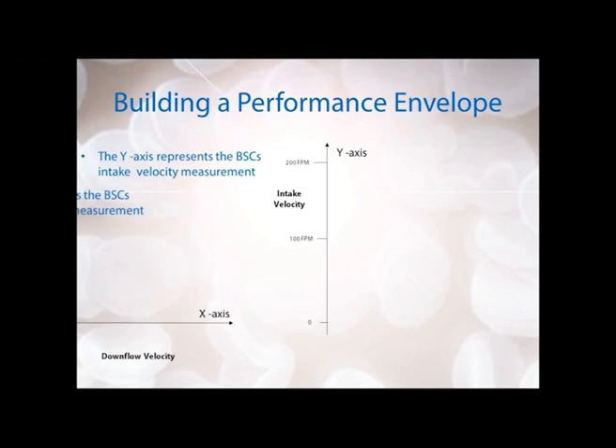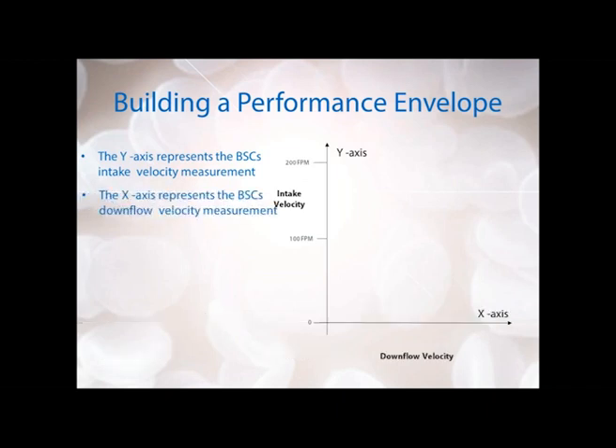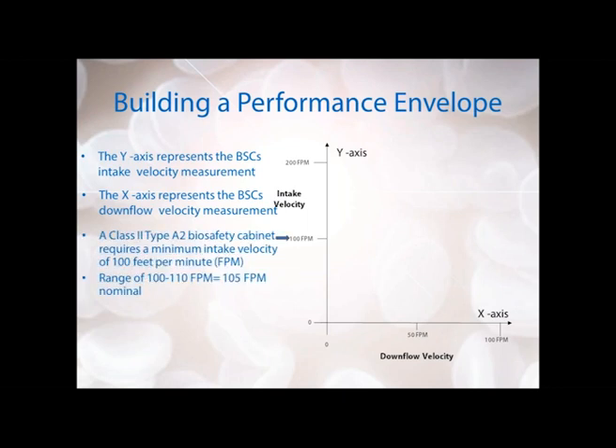We're going to use those two aspects to build our performance envelope. On the y-axis of this graph we're going to plot our intake velocity, and on the x-axis we'll plot the downflow velocity. A Class 2 A2 biosafety cabinet requires a minimum intake velocity of 100 feet per minute, as specified in NSF Standard 49. Due to the restrictions of the instrumentation used to measure airflow velocity, there's a variance range of about 5 feet per minute. To ensure you never go below 100 feet per minute even due to instrumentation variation, the nominal set point of the intake velocity will often be set at 105 feet per minute.